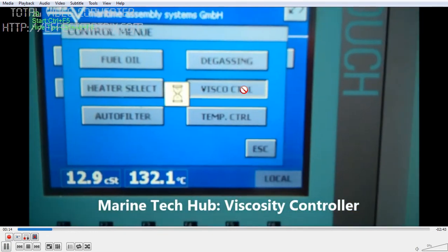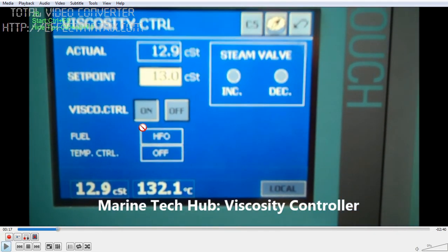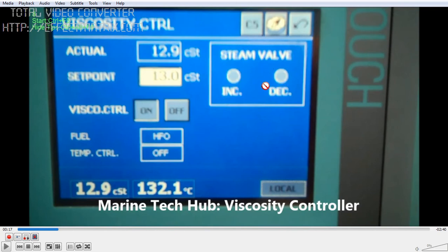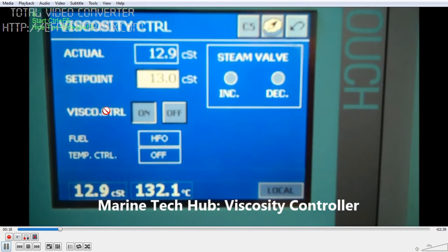You can see the viscosity control. Right now we have set the viscosity control to 13 centistoke. We have the viscosity control on and off — right now it is on. So it will be maintaining the viscosity. You have the steam valve which will be opening and closing. All the signals are interlinked. Now the temperature control is off — we are using the viscosity control here.